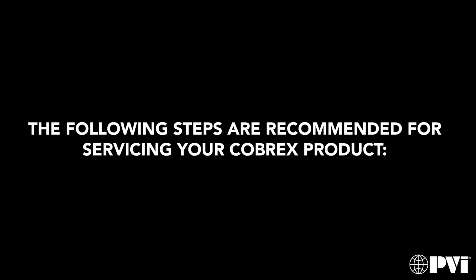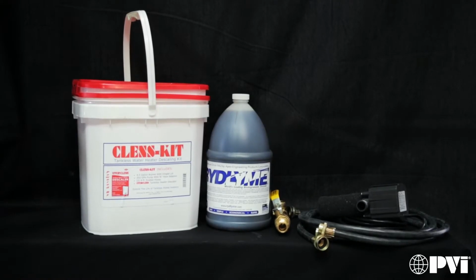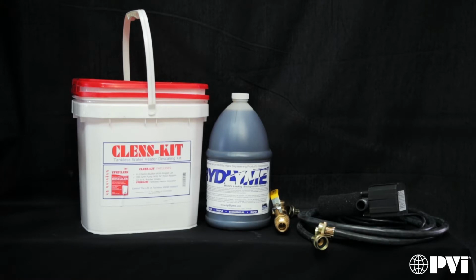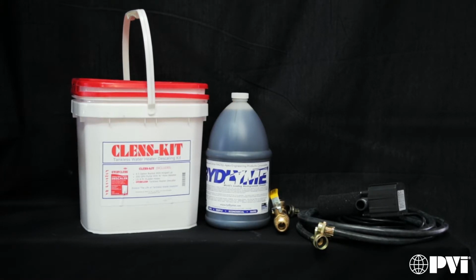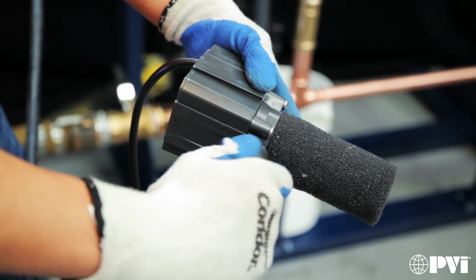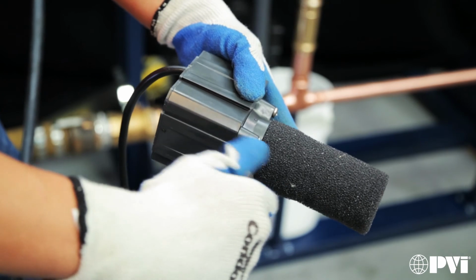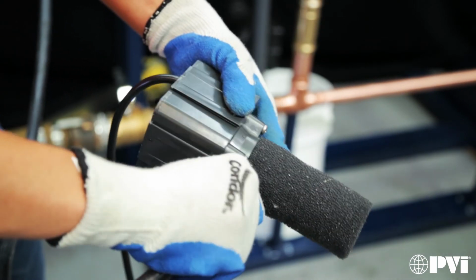The following steps are recommended for servicing your Cobrex product. To clean the heat exchanger, you will need a 5-gallon bucket, cleaning solution, wrenches, tubing, a pH test kit to measure acidity level, and a submersible pump compatible with the cleaning solution and able to flow 3 gallons per minute against 5 feet of head. A larger pump with a throttling valve on downstream tubing will also work. Prepare the cleaning kit by connecting the hose to the pump. Place the 5-gallon bucket under the bottom clean-in-place fitting.